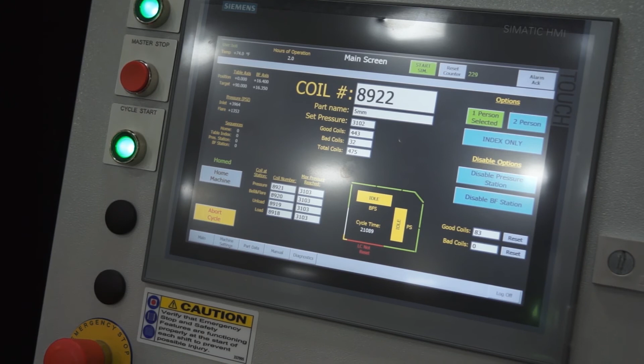The best feature of the Phoenix Expander in my mind is the manifold design and how we achieve the clamping and sealing of the coil. We went to a sealing method that is independent from any oils, so no matter what kind of oils you have here, it'll clamp and seal. From the control perspective, we tried to design the pressure expander to be easy to set up with an easy operator interface and quick changeover between different coils.